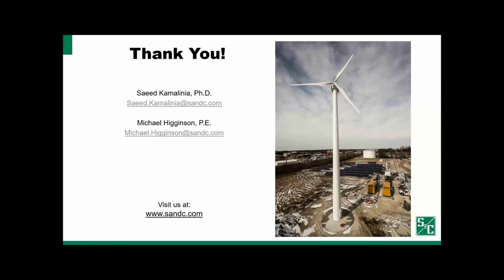Oh, here we go. So the question was, do you think inverter-based resources should also provide negative sequence current? And that with the context that Maddie sees some new grid codes coming out in this respect, asking inverters to provide this current during faults. Yeah, I would echo the latter part of that. There's definitely grid codes and IEEE and other industry standards that are leaning towards requiring resources to be capable of supplying negative sequence current.